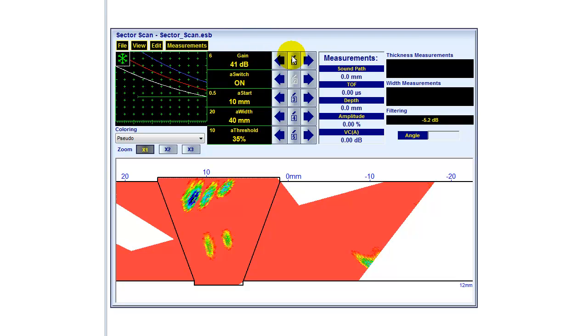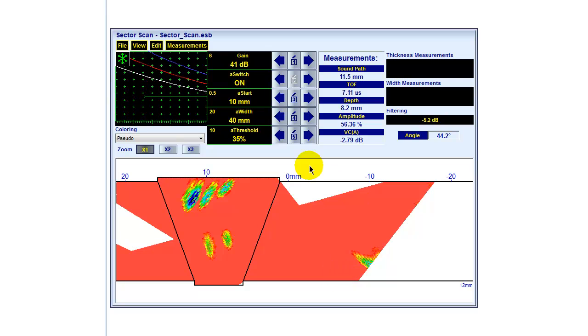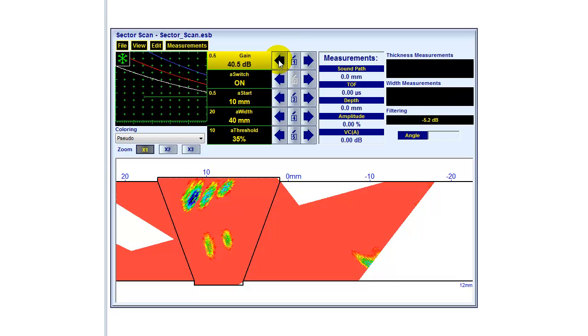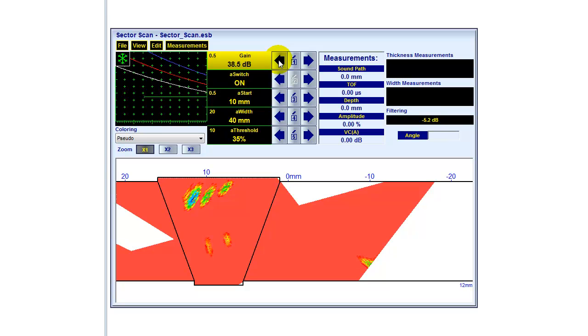As I already mentioned, we have stored the raw data. So, we are always using the raw data to reproduce this picture. And in fact, that also means that we can change the gain settings later on in this post-processing software. And I am doing this now, just reducing the gain. Let me do that in smaller steps. And one can see how the results are changing. Because I just do some filtering, putting the gain down in this case.